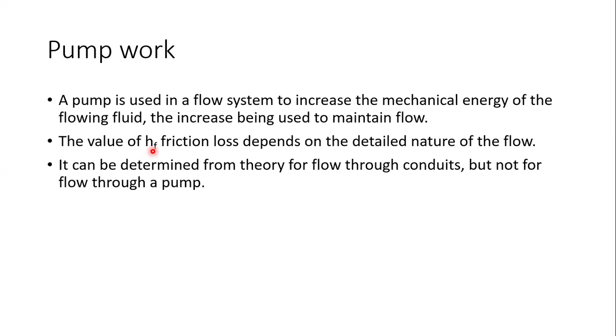So what they're trying to say is that we can find HF when we are looking at pipes, when we are looking at channels that fluid flows through. But when we are doing it for pumps, it becomes difficult. You can't easily find HF for pumps, the friction effects in pumps, right? Friction occurring within a pump is due to not just the fluid friction, but the mechanical friction as well. That's why it's a bit difficult to determine it from just theory or from just calculations, right? So the mechanical energy that we give to the pump as negative shaft work must be discounted by these frictional losses to give the net mechanical energy actually available to the flowing fluid.